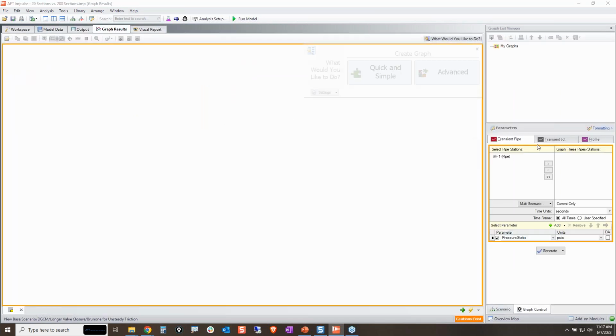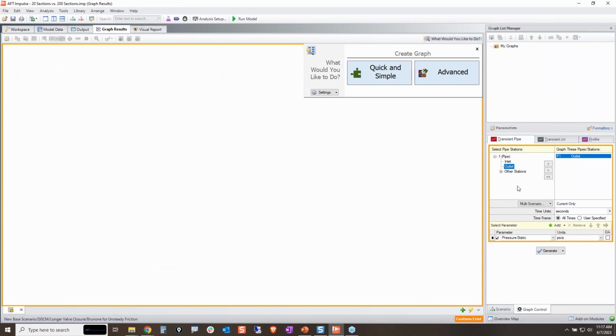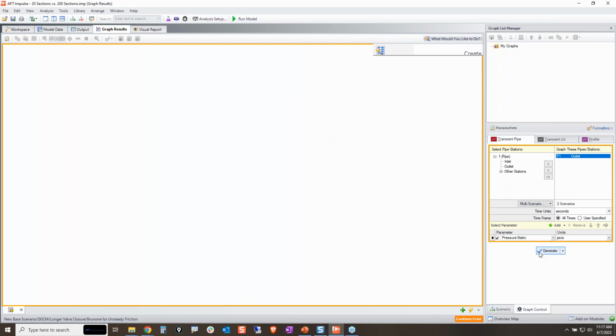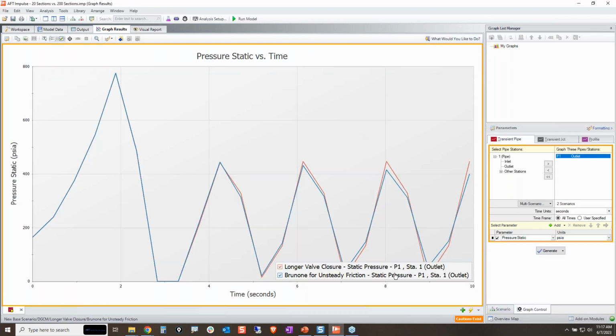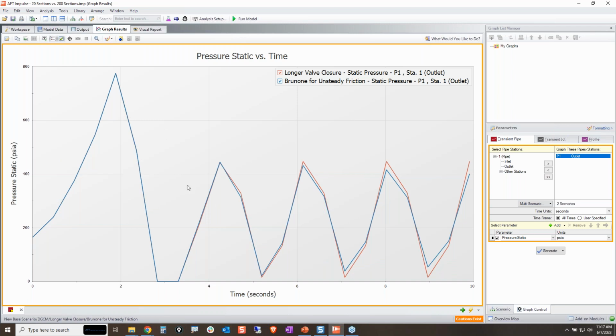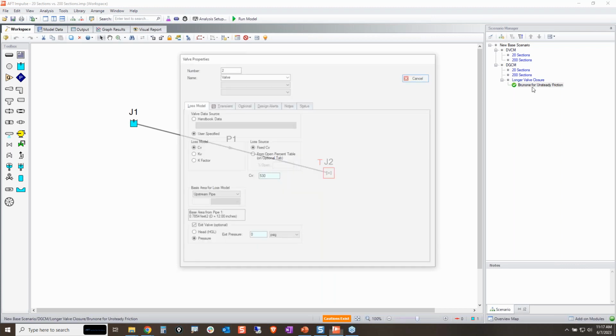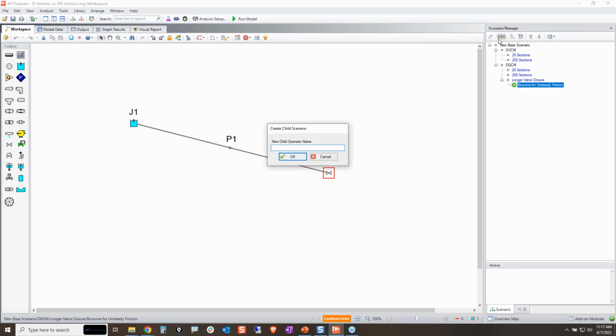So if I look at that same area for pressure for both the scenarios, well, they're very similar to each other. And so this gives me good confidence as to what's happening. Well, if I was able to eliminate cavitation or the majority of it simply by closing the valve within 2 seconds instead of 1 second, another thing that you can try doing is the 80-20 rule.